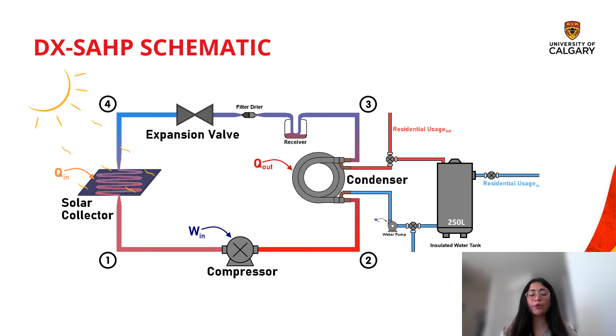To meet our design heat load, the first step was sizing our solar thermal collector to determine the useful heat gain we could extract from it. To quantify the heat gain, it was important to characterize an overall heat loss coefficient, so as designers we wouldn't minimize solar energy gains by undersizing the flat plate collector or maximize losses by oversizing it. It was a balancing act, so we conducted an energy balance on the plate, as seen in the diagram.